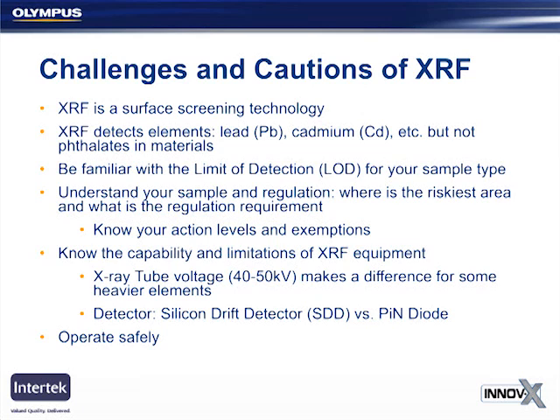There's another example. RoHS has some exemptions for certain materials. For example, steels have a higher lead exemption limit than the standard 1,000 ppm. And so you want to make sure that you're applying the correct action level to the material that you're testing. You want to know the capability and limitations of the particular equipment that you have. There are a couple of specs about XRF equipment that I'll go over briefly.